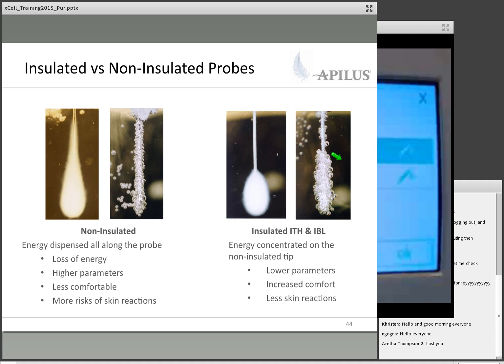As far as using insulated versus non-insulated probes, using non-insulated probes just means that you have a much bigger surface area. And usually with currents, even though you have slight differences in how the current is dispersed along the probes in high frequency versus galvanic, you still have essentially loss of power higher up on the probe where it's not necessary. So our target is, on an anagen hair for example, the bottom two thirds of the follicle. So the top third, where you have the upper layers of the skin, you don't really need energy up there, and coagulation to happen or lye to be produced. But because the probe is in contact with the tissues, there is going to be some energy up in those upper layers of the skin. So with a non-insulated probe, you have loss of energy up here where it's not necessary.